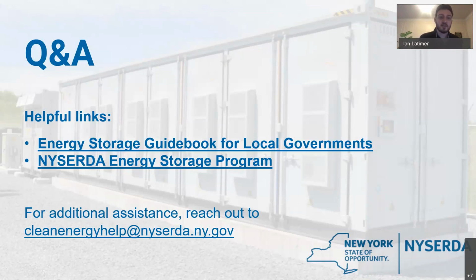You have sensors for gas buildup or pressure buildup. There are also sprinklers installed in some systems. There's also what's known as deflagration venting sometimes installed, meaning that once pressure inside the container builds up to a certain point, it will blow the panels to ensure that pressure cannot continue building up in the event of an imminent explosion.